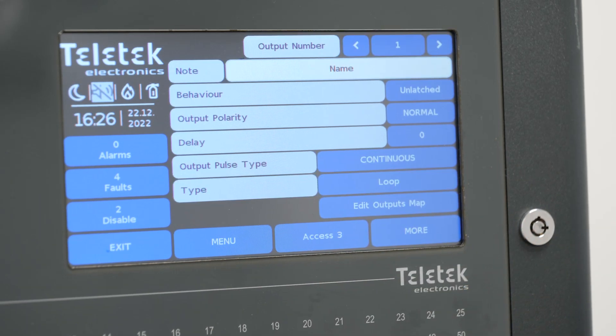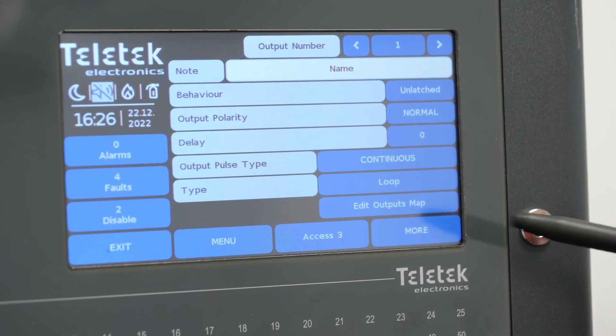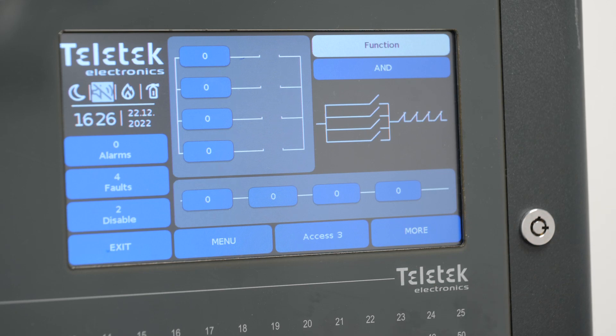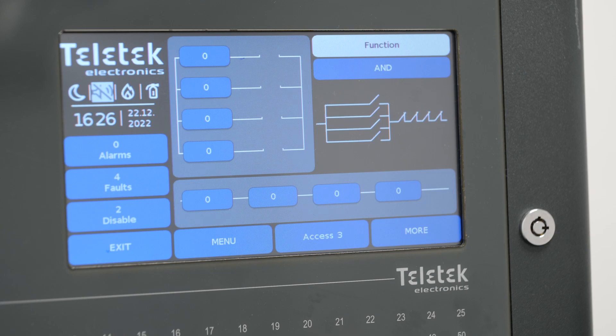Final step is editing the output map. Output map is the connection between the inputs and the output. In our case, input 1 representing fire in zone 1 or input 2 representing the fire in zone 2 should activate the Mio 22 output.